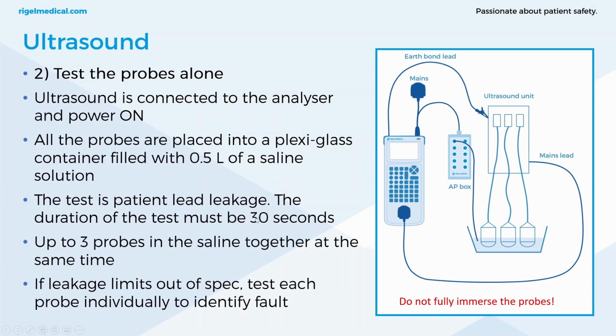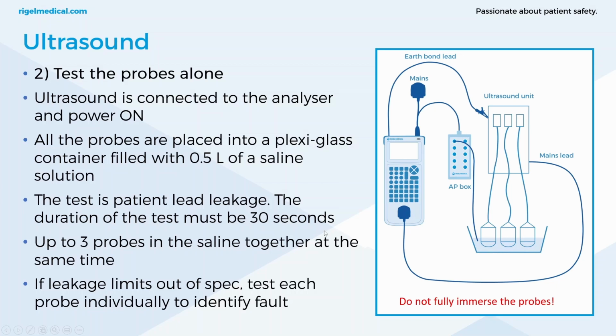The duration of the test is 30 seconds, and that just ensures that the saline gets a good contact between the circuitry, electrode within the probe, and the patient leads. And that's just what we recommend. But it's always best to just contact the manufacturer when it comes to these types of tests.